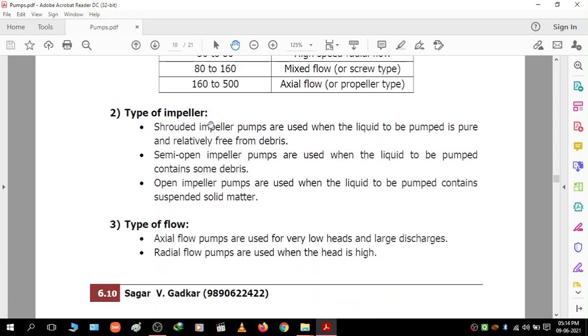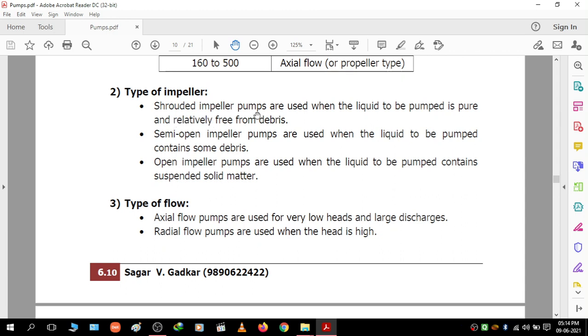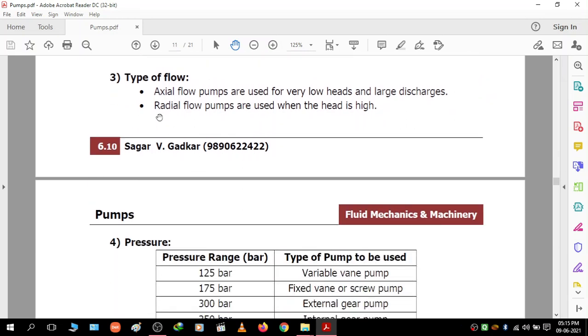Selection based on type of impeller: Shrouded impeller pumps are used when the liquid to be pumped is pure and relatively free from debris. Semi-open impeller pumps are used when the liquid contains some debris. Open impeller pumps are used when the liquid contains suspended solid matter. For type of flow: axial flow pumps are used for very low head and large discharges, while radial flow pumps are used when the head is high.